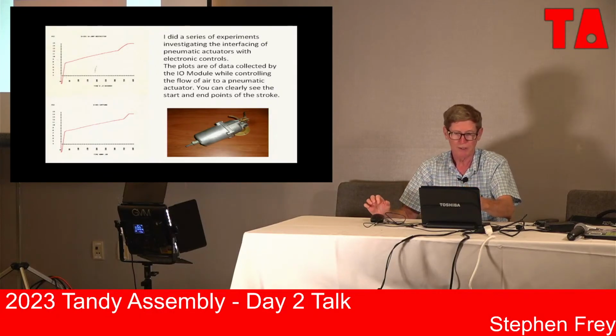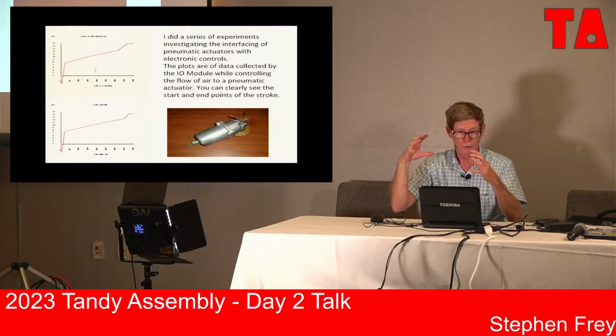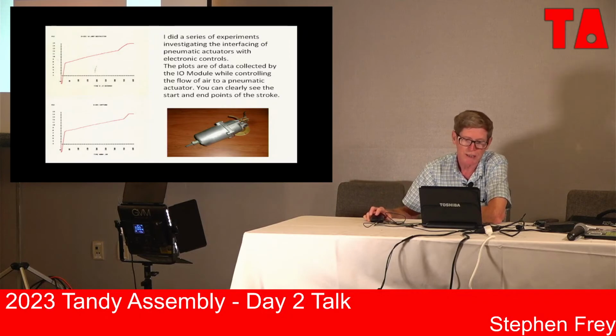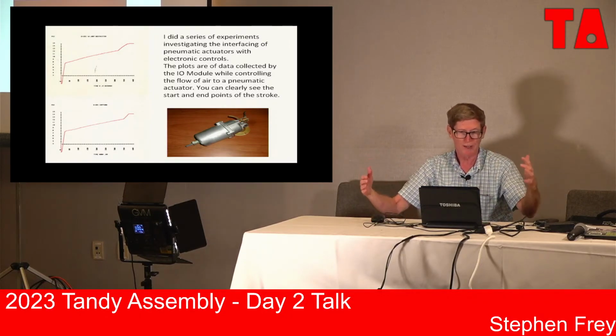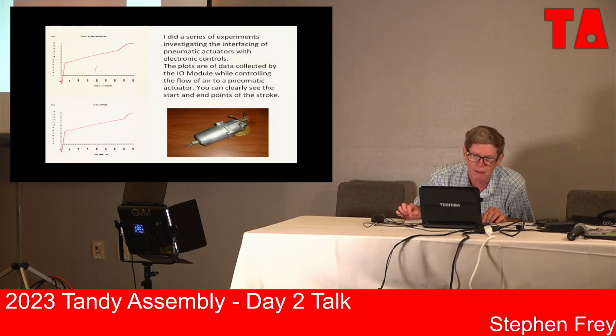Then it goes up at a less steep angle, because now it's a bigger volume. So you can not only see what the volume of the actuator is at that point, but you can also see the stroke and the endpoints of that. You can read off of that - the thing operates from just under 8 psi to probably 12 psi or so.